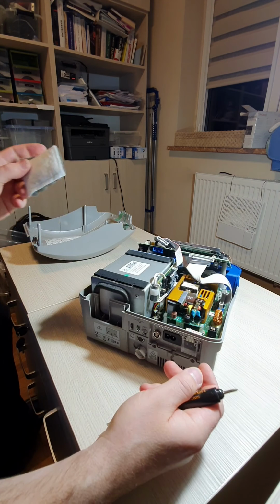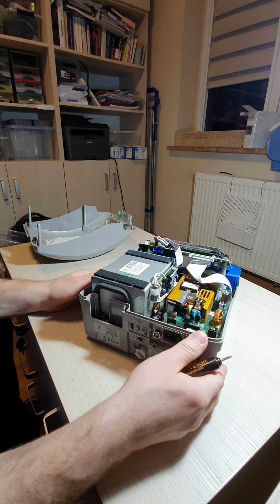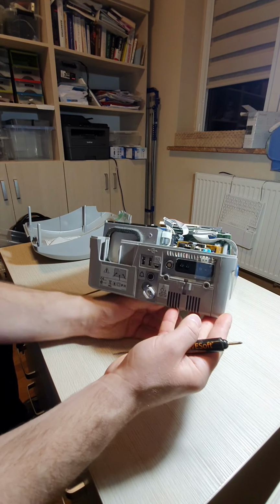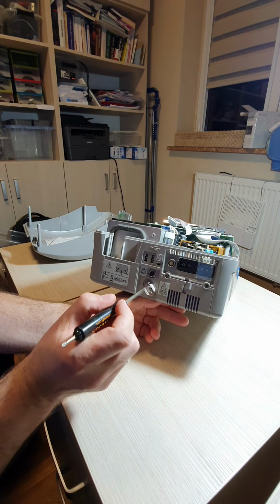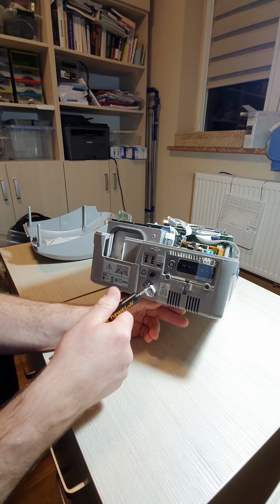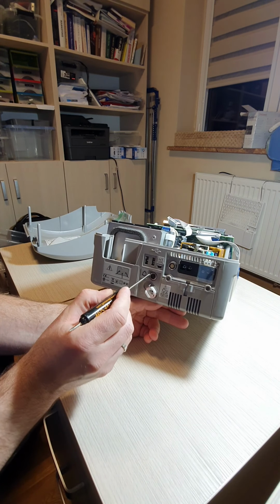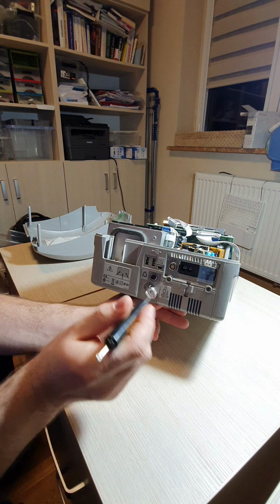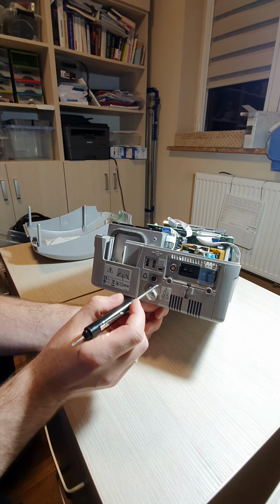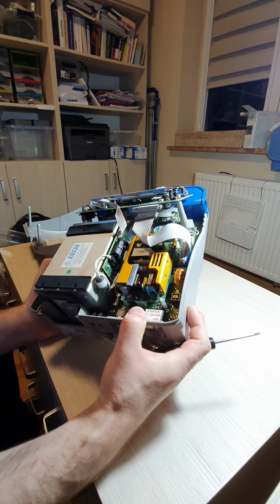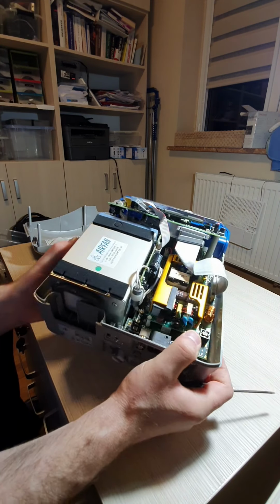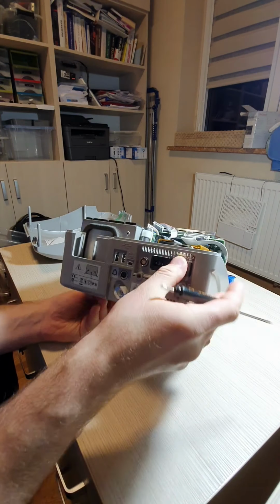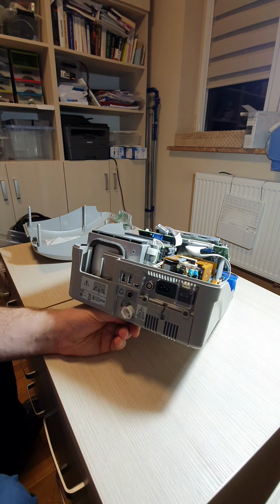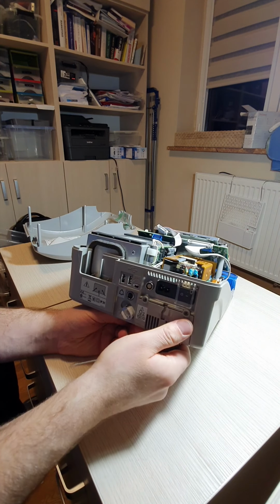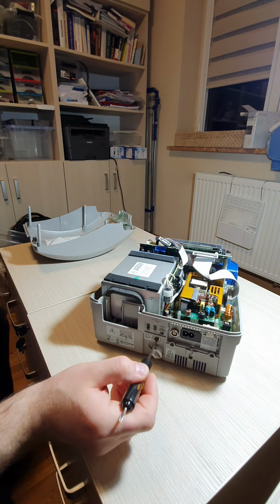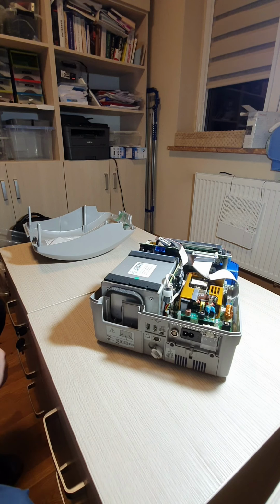This is the filter, which filters the air which is sucked from the outside. Here's the output. This is the panel. Here we apply the pure, pressurized oxygen. Here's an alarm connector. It's a Lemo, and essentially what it does, it has a relay. It should sit somewhere here. It's not visible actually. The harness goes to the CPU board. So it's an NC, normally closed contact, the relay. When something goes wrong, it's plugged into the alarm installation in a hospital.